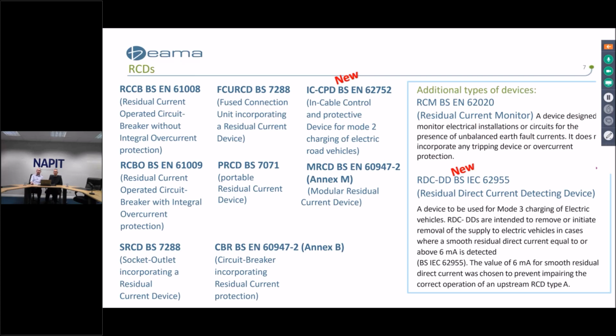And just going to the bottom of the next list, the modular RCD is BS EN 60947-2, and that's where the RCD is not built into one unit, but it's a number of different modules that are wired or connected together. The two new devices, which are relatively new to the market, is the ICCPD, which is an in-cable control device for protection of electric vehicle charging under Mode 2, and that's BS EN 62752.